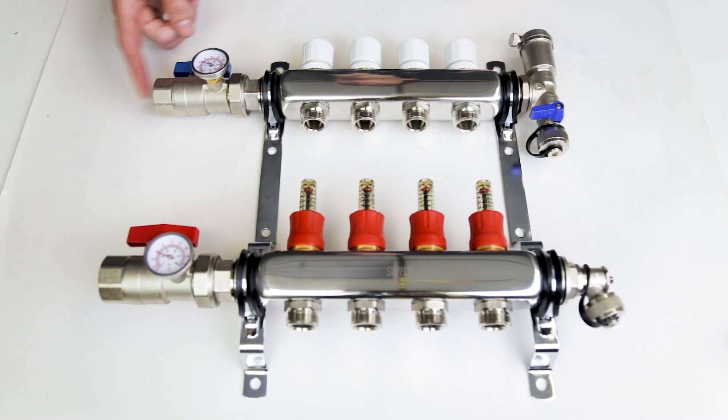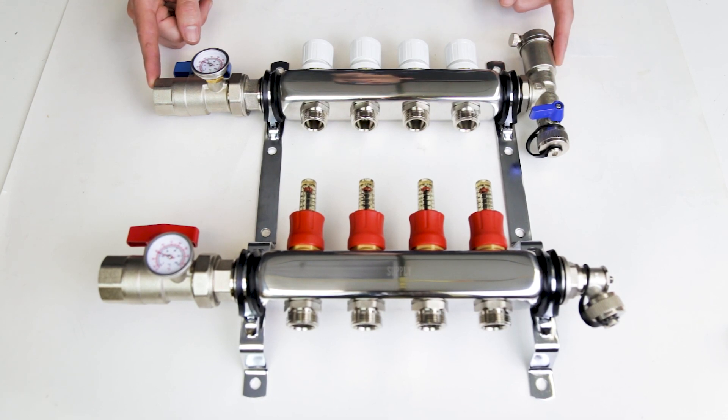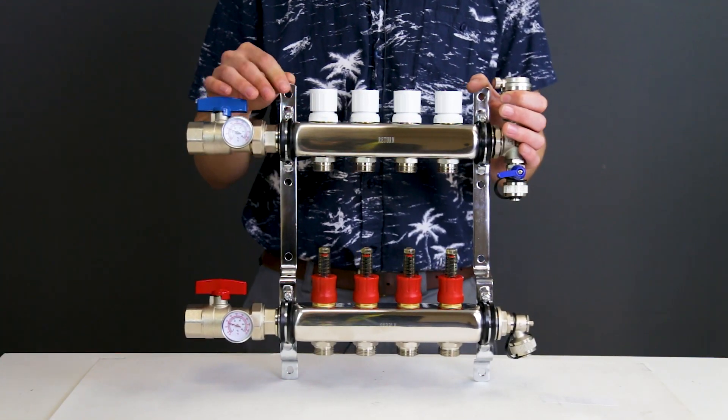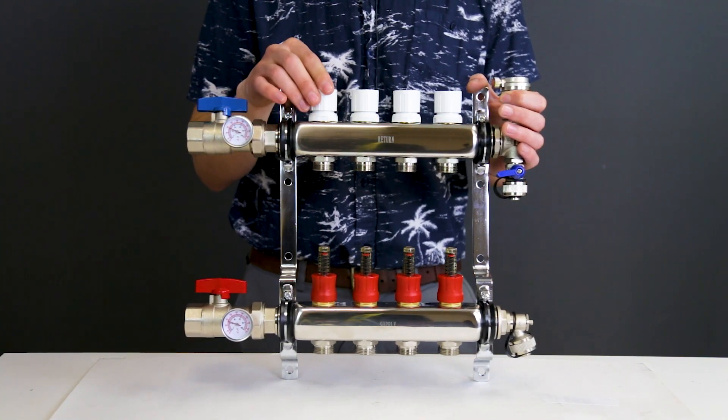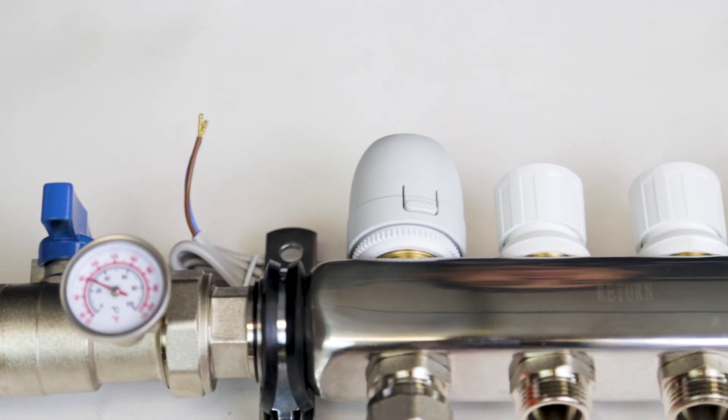Our manifold here has the standard one inch screw on connections. On the top, we have an automatic air vent. On the bottom right side, we have the drain connection. We have temporary decorative caps on the top rail. They are used for isolation and adjustment of each circuit. There is an option to replace them with electronically controlled actuators.